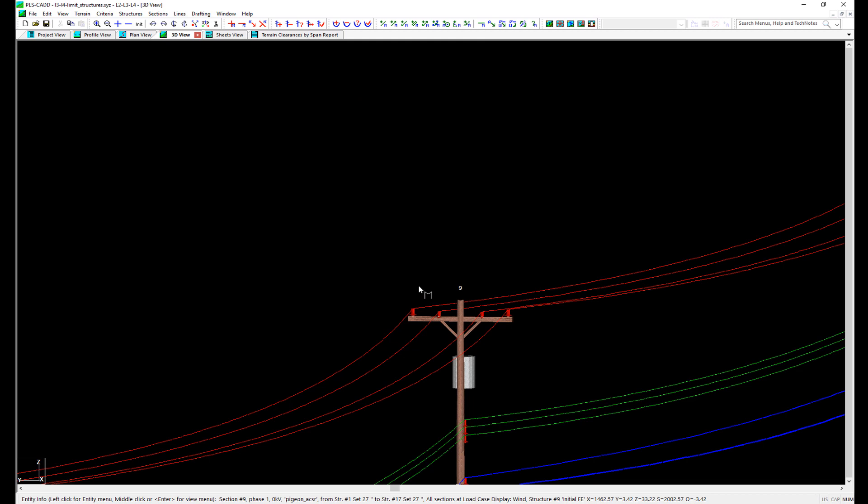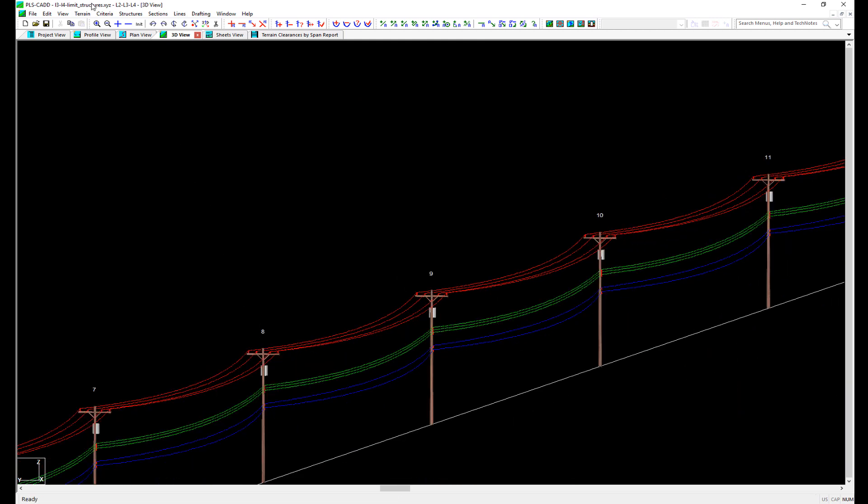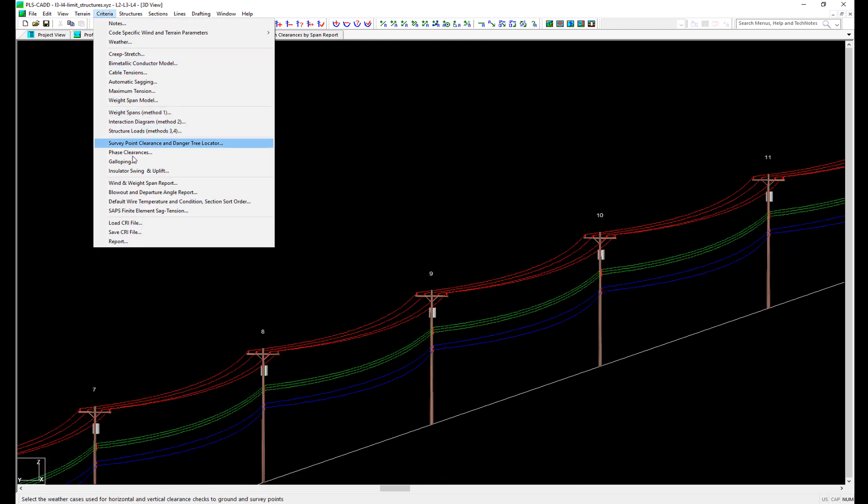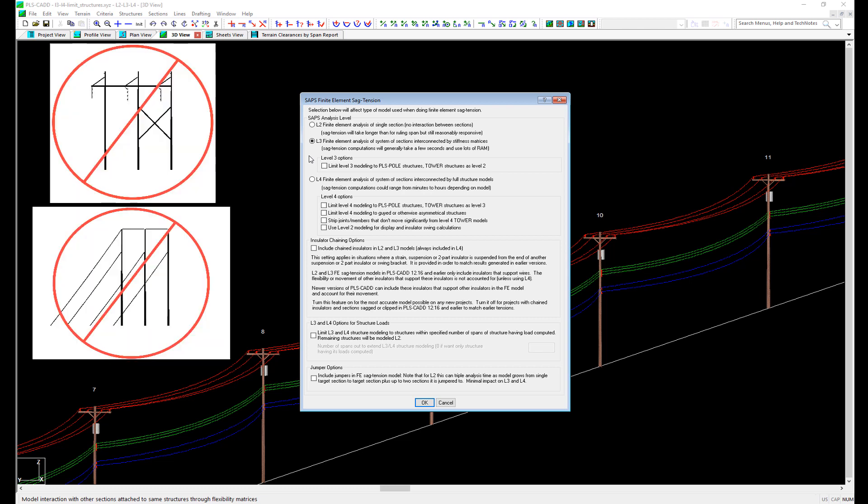Now let's take a look at the next higher level of SAP's analysis, L3. We navigate back to Criteria, SAP's, Finite Element Sag Tension, where we can select the option for L3. SAP's level L3 analysis will take structure deflections into account by using simple stiffness matrices or springs at each wire attachment point. One important thing to note about SAP's level L3 analysis is that it is not applicable to guyed or asymmetric structures, since those structures have a different stiffness in one direction than the other.